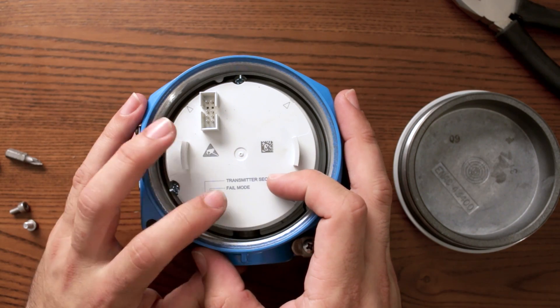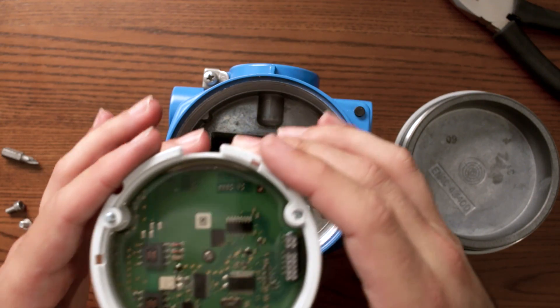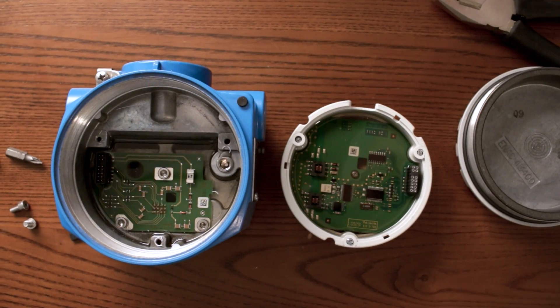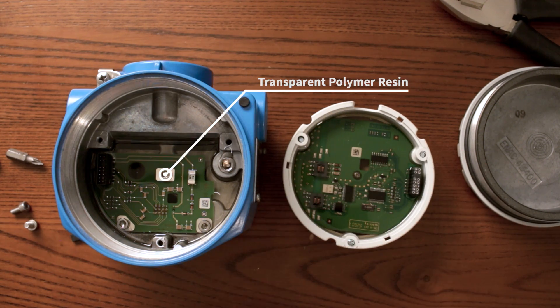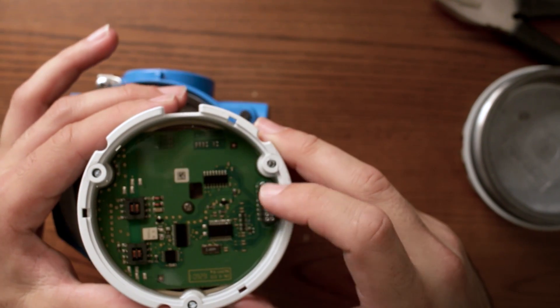Here you have the connectors, and here you have some transmitter security and fail mode settings. Let's see what's inside. Here we have the electronics, and here you'll see why these devices are so reliable. Because if you see here, it's full of glue — these circuits are completely protected by glue so that no humidity is able to penetrate the electronics. The only connection between the terminal block behind and the actual electronics of the transmitter is done by this block here.